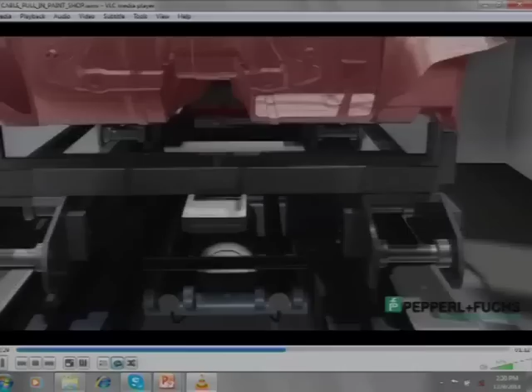Self-diagnostics and fail-safe. Suppose the sensor fails, what happens? What are the fail-safe measures which are taken? Otherwise, a severe accident can result. Sir, in case of fail-safe, what happens is, suppose you are using a sensor in NO mode, automatically the fail-safe sensor will go back to its normal mode condition, it goes into a stay put condition. Yes, stay put condition.